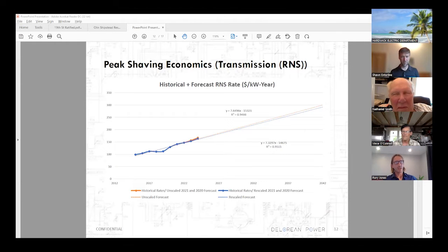So you have 12 monthly coincident peaks and one single annual coincident peak. Our entire reason for being is to discharge the battery during those 13 hours of the year. In order to do that with sufficient margin of safety, we have to discharge it more than 13 times a year. Every time we think it might happen, we've got to position the battery and discharge it. So call it 50 to 60 times per year, we are discharging the battery fully during an event we think could be the coincident peak event, either the single annual or one of the monthly coincident peaks.